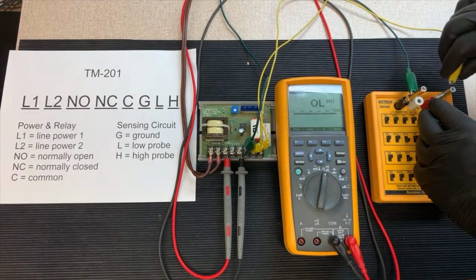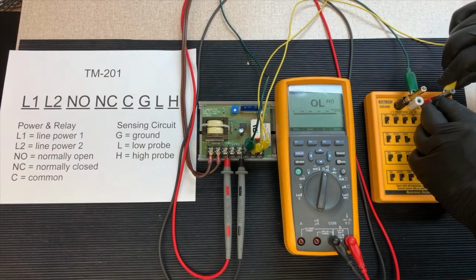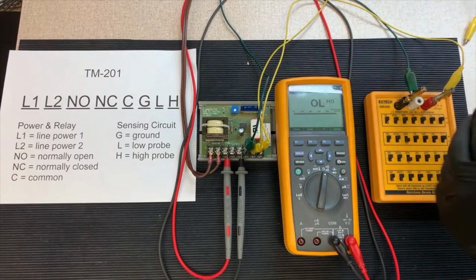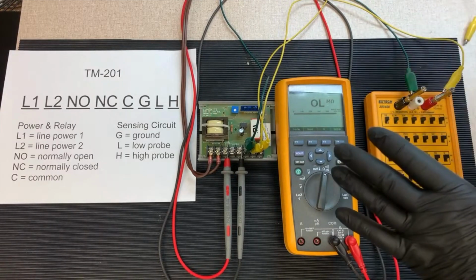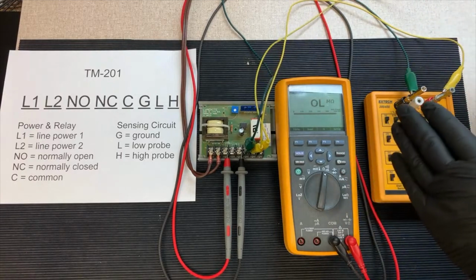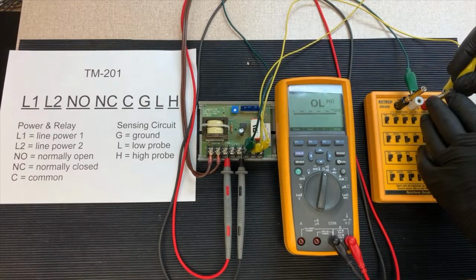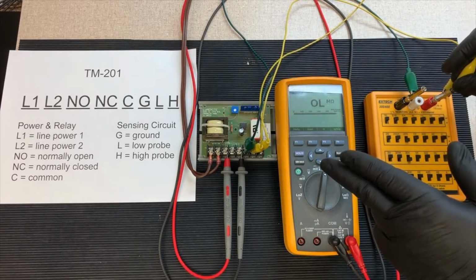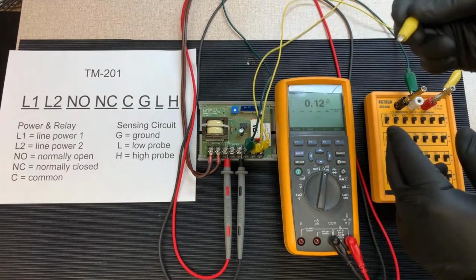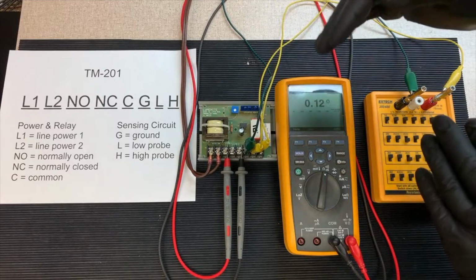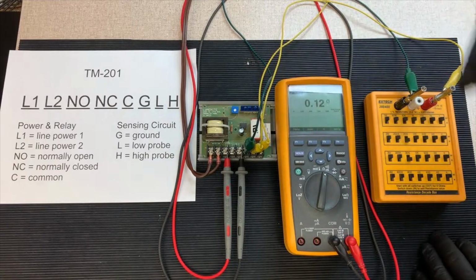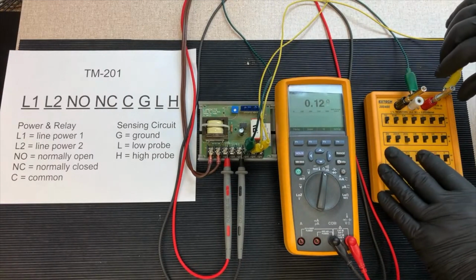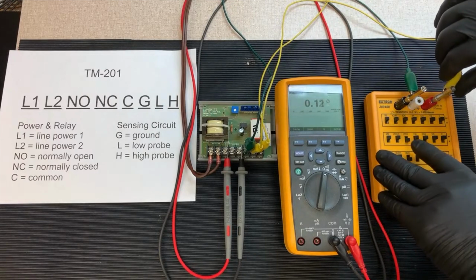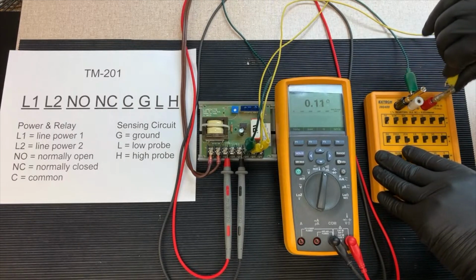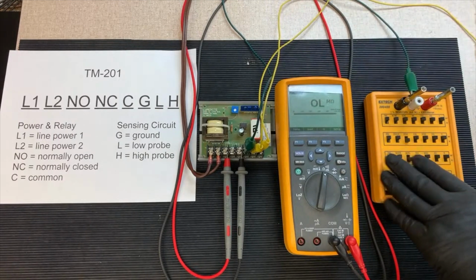When you hook the low probe up, it's going to act like there's liquid in a tank filling up on two probes. When liquid hits the low probe, nothing happens. But when liquid hits the low probe and the high probe, you're going to see the relay energize. And then even though liquid drops off the high probe, the relay is going to stay energized until liquid drops off the low probe. And in this case, when we take the low probe clip off, the relay de-energizes immediately.